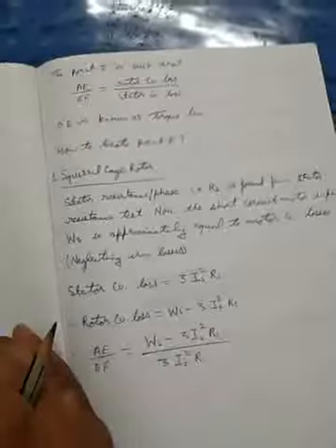Now, we have two types of rotor. One is the squirrel cage rotor and the other is the wound rotor. For the squirrel cage rotor, the stator resistance per phase, that is R1, is found from the stator resistance test. The short circuit motor input WS is approximately equal to the motor copper losses, neglecting the iron losses.